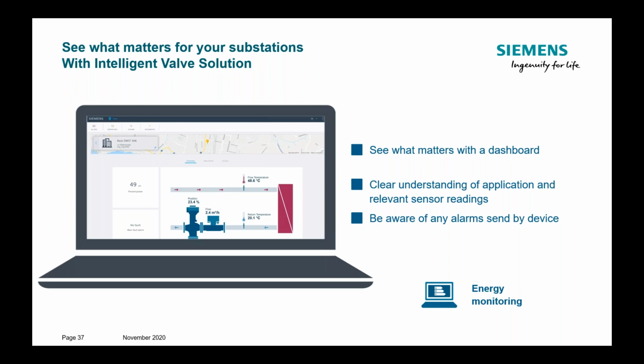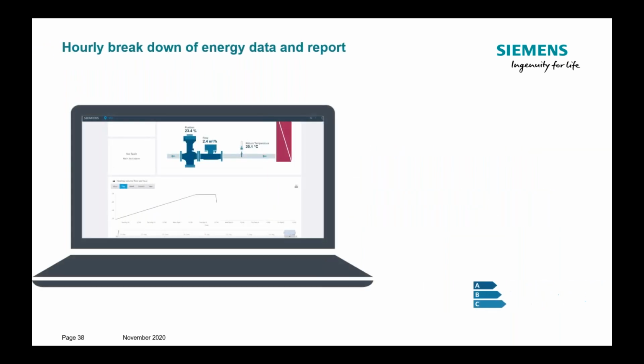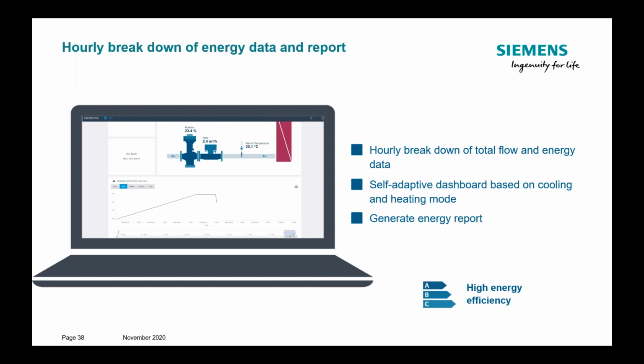And on the second level, you clearly get energy reports and data out of this. So you can do hourly breakdowns of the energy provided in the network. You have the dashboard, and you can export these energy reports out of this solution for your later optimization of the building. In addition, this also for sure allows you to interact with the devices. So if you have alarms, you can run test cycles on the device. Also, you can remotely change parameters on the device.